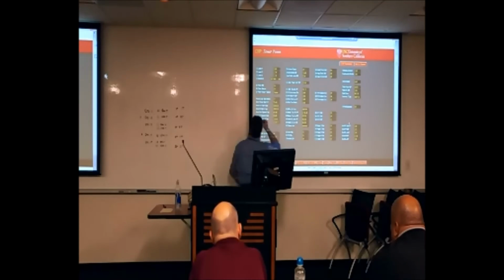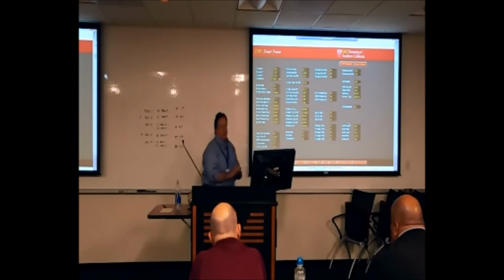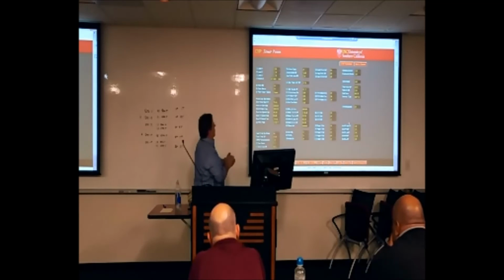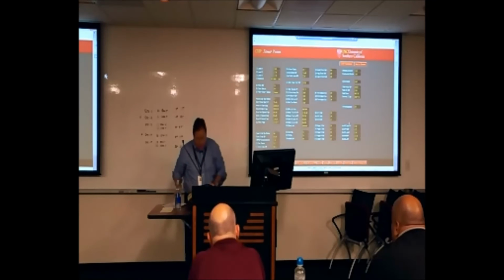Here's information related to the condenser water pumps. And there are 2 modes of operation we have for those pumps. One is a fixed speed mode, which is currently in right now, just running a fixed 75% on the pump. The other mode would be, if the fixed speed mode is off, then it's going to run the variable speed mode.